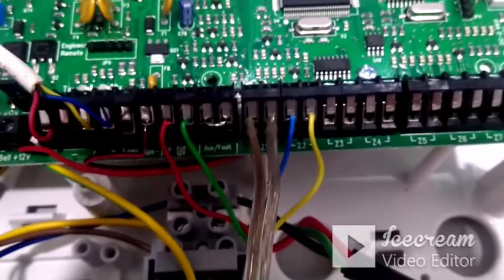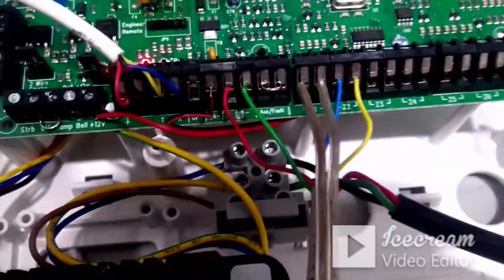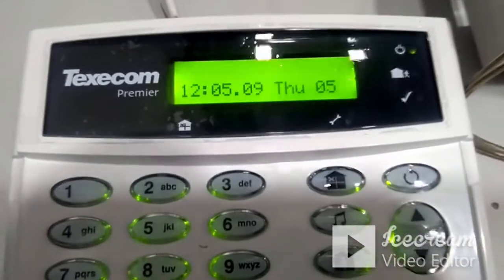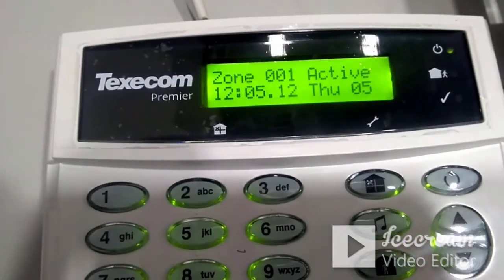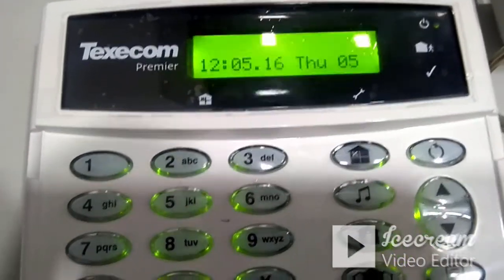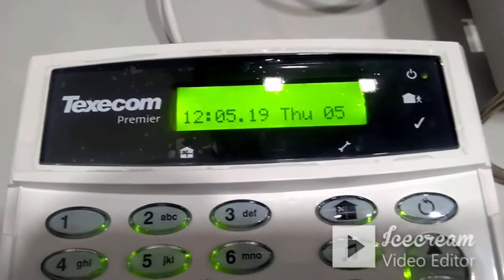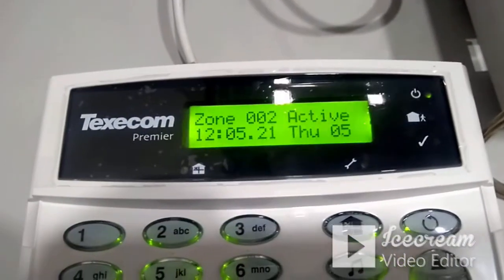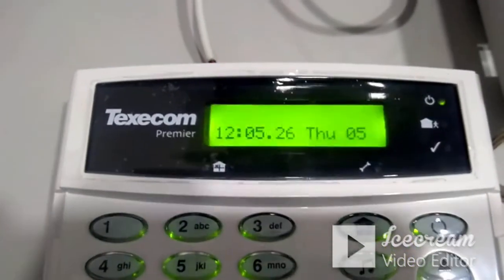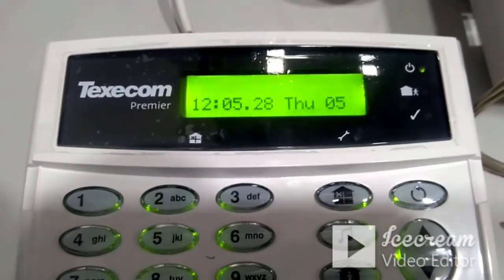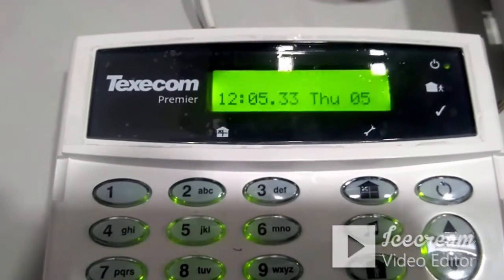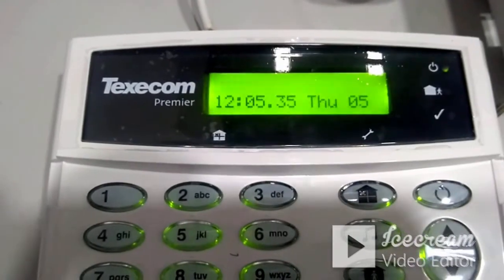To check sensor status: open the door sensor and zone 1 shows as active on the display; close it and it returns to normal. Vibrate the vibration sensor on zone 2 and it goes to alarm condition. This is the initial level of testing the panel and sensors before commissioning the system.